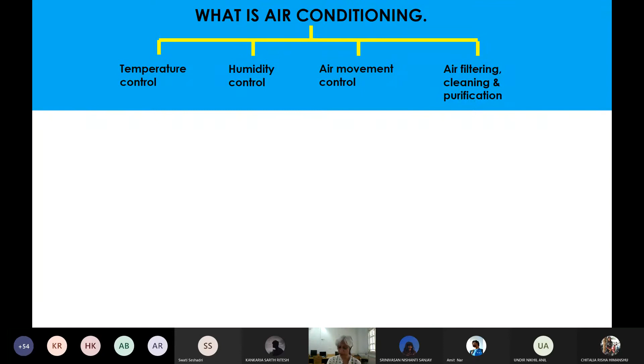Obviously, temperature cooling or heating is done at the AHU level as well as at the AC level. Humidity control happens at the AHU level. What is AHU? We will be doing it. This is just for you to understand what is happening where. Air movement happens at the room level, so like in your split AC, you can change the movement of the louvers up and down, sideways. And finally, you have air filtering, which happens again at the AHU level. It does not happen at the plant room level. Cooling happens in the plant room, but control happens at the AHU level.